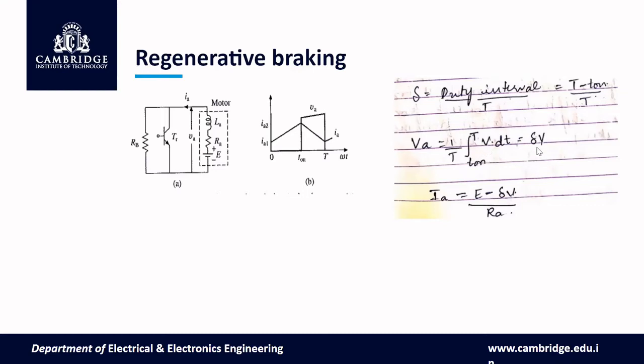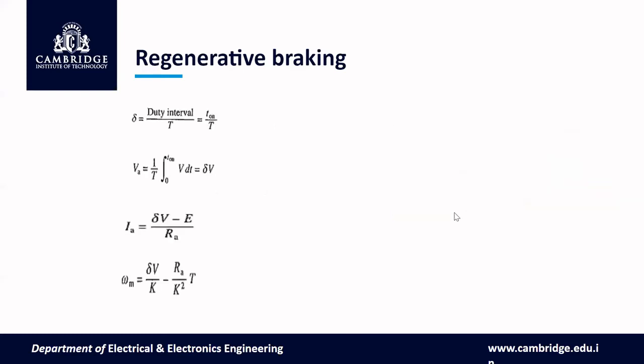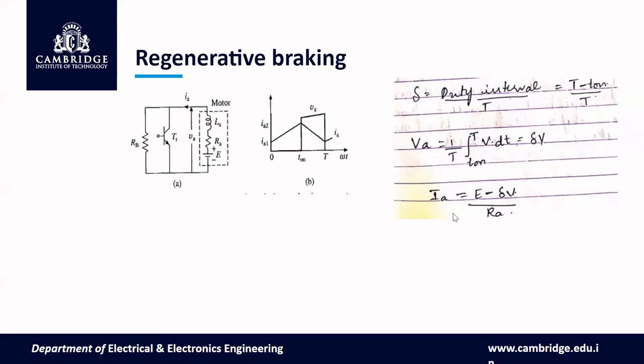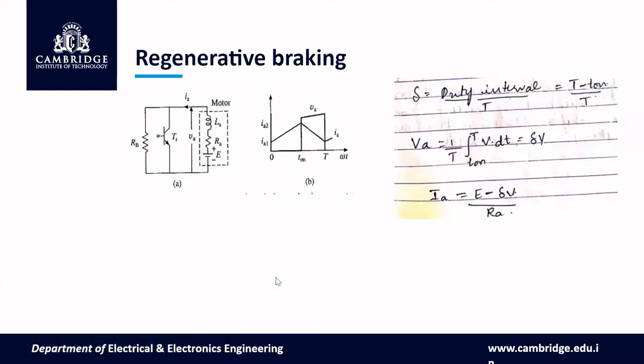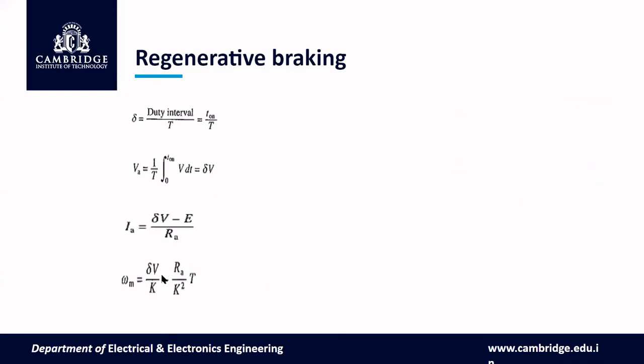For regenerative braking, Va = (1/T)∫(Ton to T) V·dt = δV. Then Ia = (E − δV)/Ra. Since Ia has reversed, T = −K·Ia, and ωM = δV/K − (Ra/K²)·T. This completes the regenerative braking operation derivation.